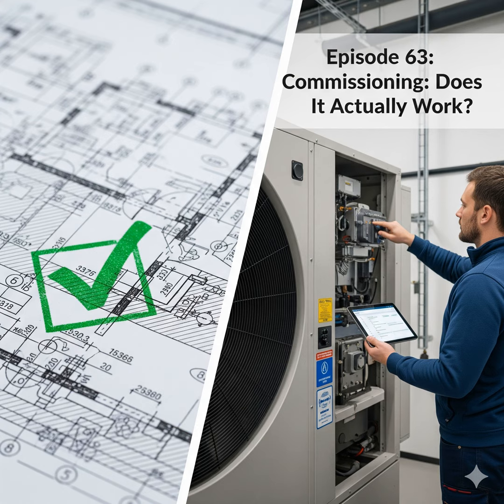Like what kind of tests? For an HVAC system, we might simulate a hot summer design day, then a freezing winter night condition. We'd test if the air handling units sequence correctly, if individual zone dampers respond precisely to temperature set points, if the central building management system accurately logs everything and responds correctly to anomalies. That's deeply checking the controls, and testing if all the interlocks with, say, the fire alarm system function exactly as designed.